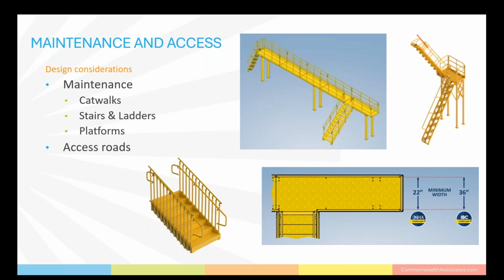Platforms need to be designed to accommodate maintenance tasks with sufficient space for tools and personnel to ensure safe access and egress routes. Lastly, the road access will initially be used for construction of the plant, bringing in construction equipment and supplies, as well as larger components of the CHP, and then ultimately for the operation of the plant. This means that there needs to be consideration for overall roadway capacity on both new and existing roads. For example, to be able to handle a long lowboy trailer with an oversized load, and the radius of the turns, we've got to make sure that they're big enough for whatever type of vehicle will be coming on site.